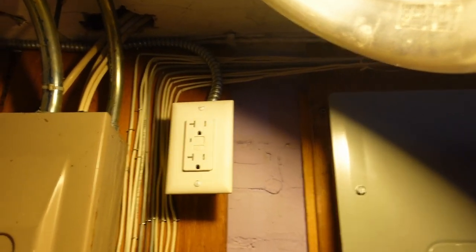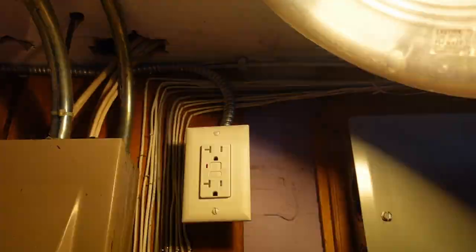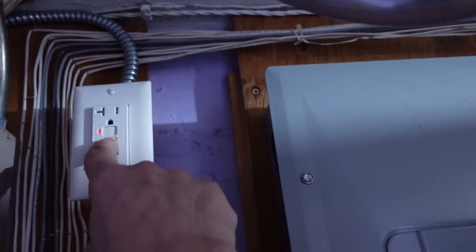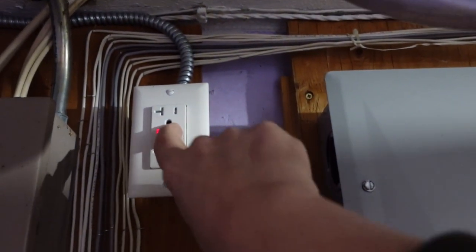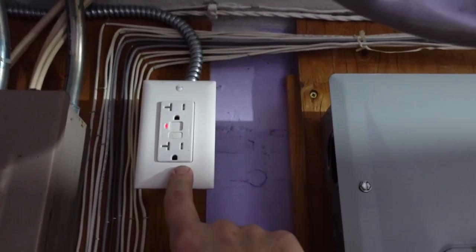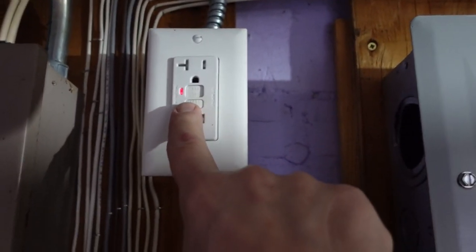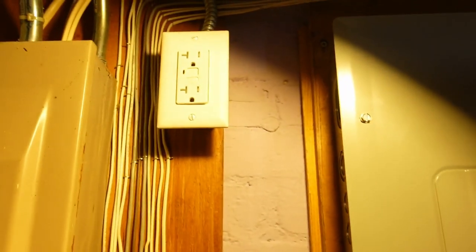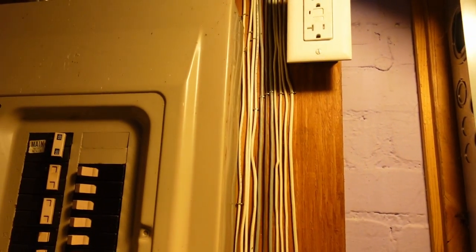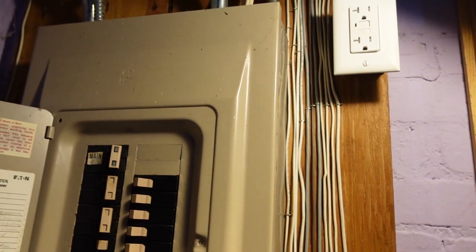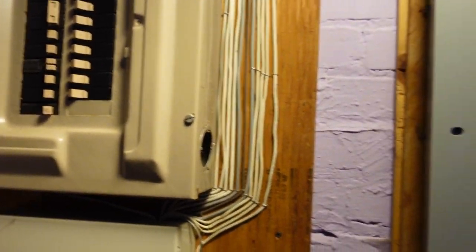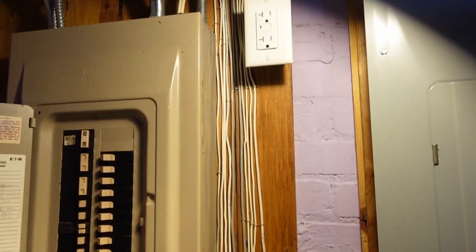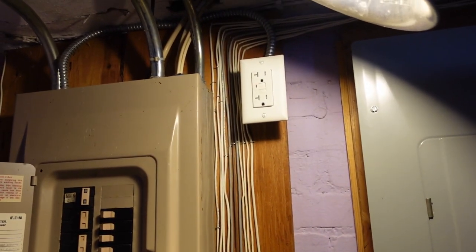It turns out that this little bugger up here—let me turn this off—it's a ground fault interrupter and it's interrupted. It's no longer working. You see that little red light right there? That is my main power for the server room, so everything in the server room went down.